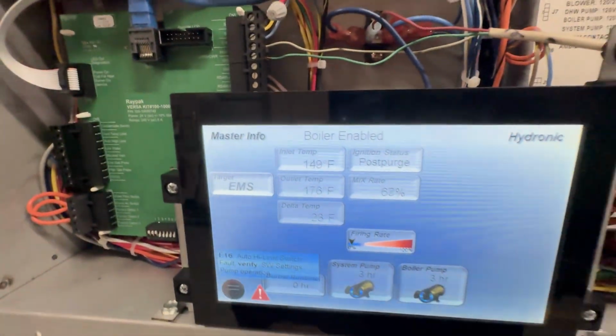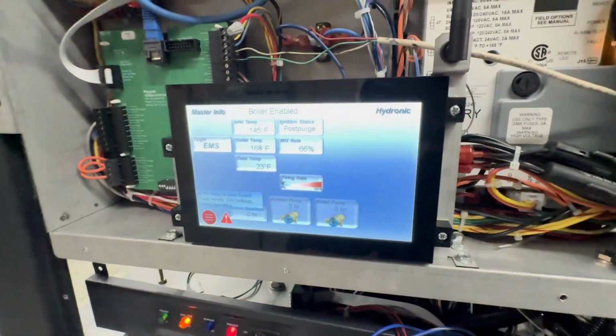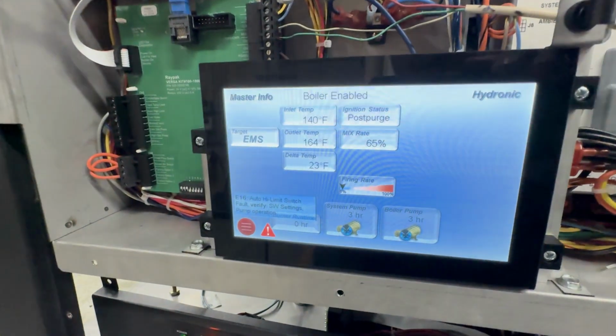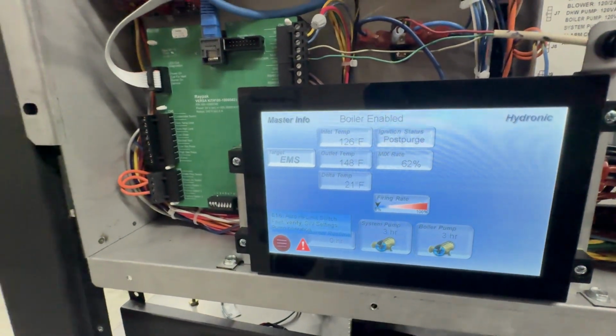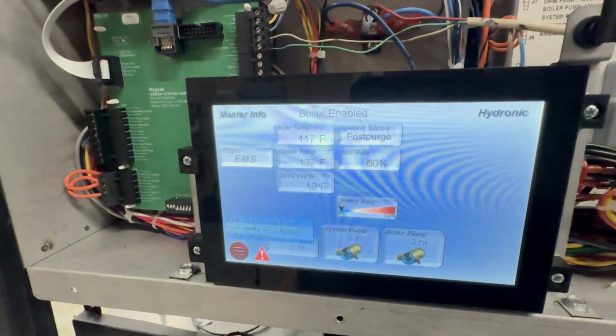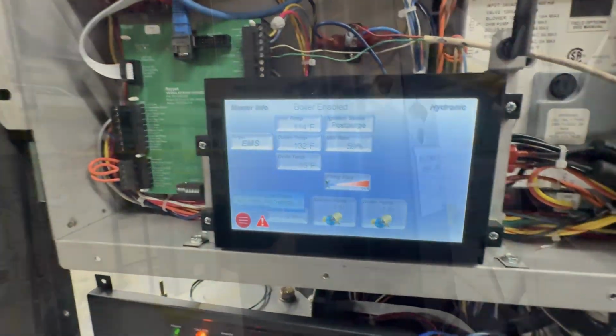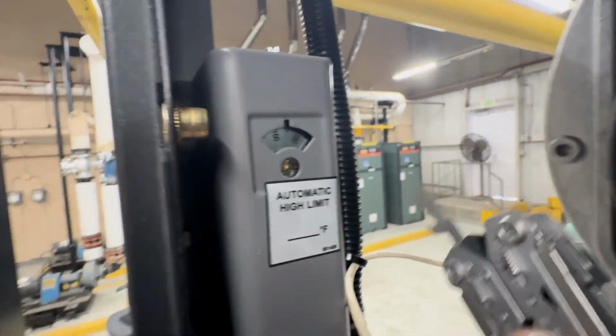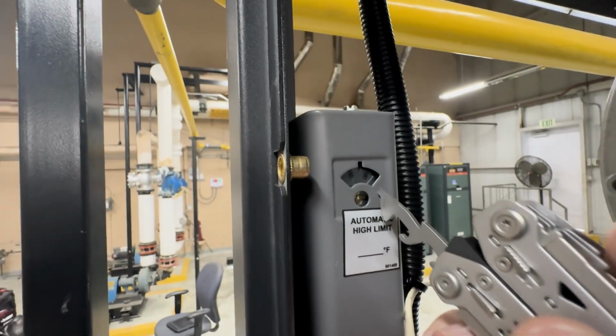We need to keep that in mind. If we're setting our high limit for 200 degrees, it looks like there's about a 13-degree differential before it trips. So if you want it set at 200, maybe set it at 190. Adjust our high limit back again.